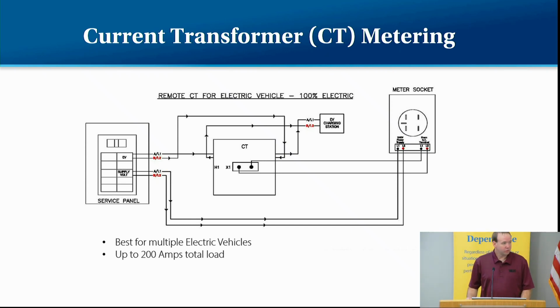You guys don't require that that's a separate circuit for that 240, that could be off the water heater, something else just to power that meter, or do they want a dedicated circuit on your end? It could be a dedicated circuit. We prefer that the circuit providing that power to any of our off-peak is off of the off-peak equipment itself. We wouldn't really want it off of a water heater for the electric vehicle, because if they shut off the water heater or get rid of the water heater or anything like that, now we won't be able to meter their use on their EV.